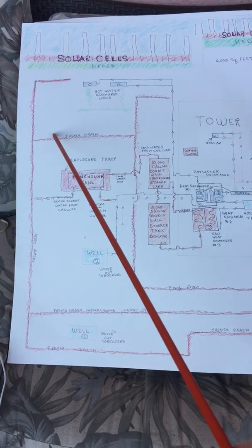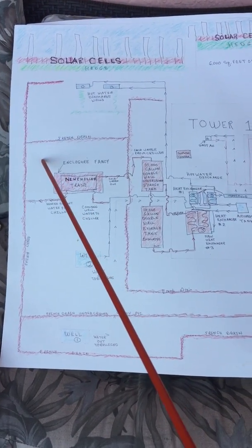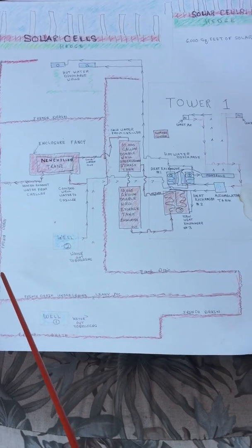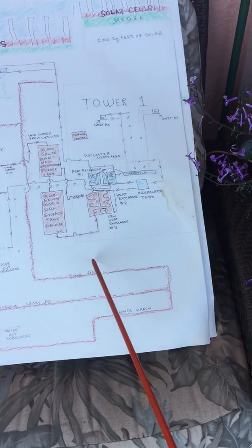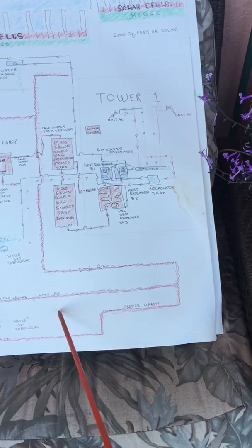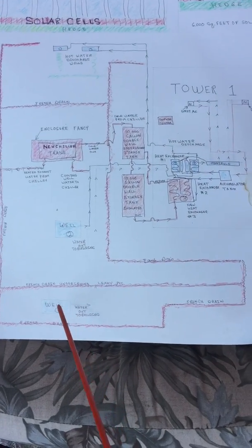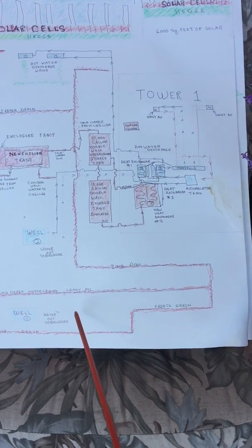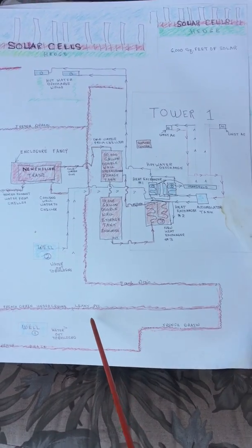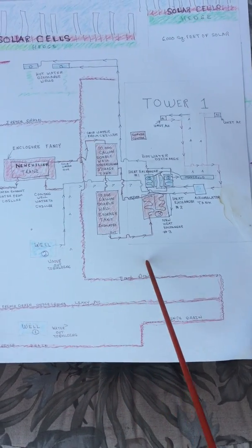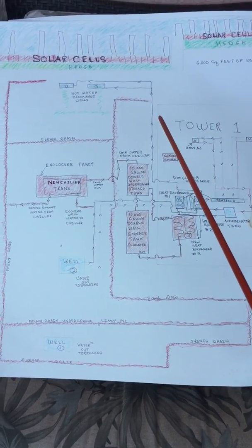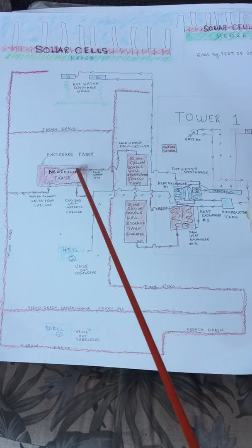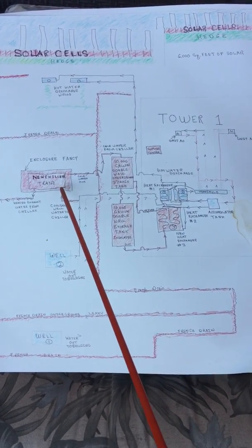Some of it will still go into the wells, but other will go and be dispersed all around. As it's dispersed through here, it takes a while to get down into the aquifer, so it cools off. So our wells will be working with cooler water, number one. Number two, they won't be running as hard, they won't have to run all day. So this underground aquifer will cool off, and they'll handle the work at night or on rainy days when we don't have power to run the chillers.